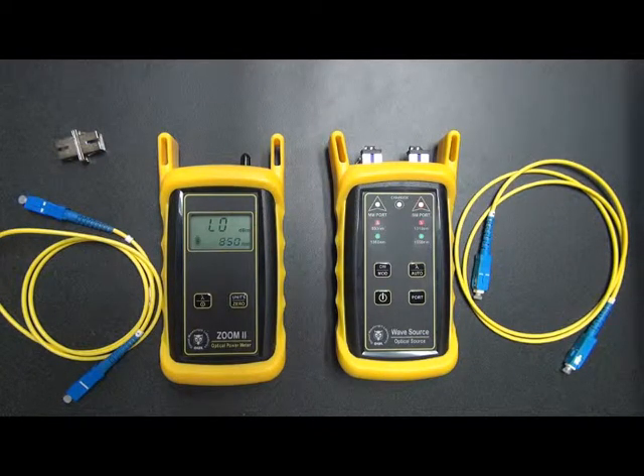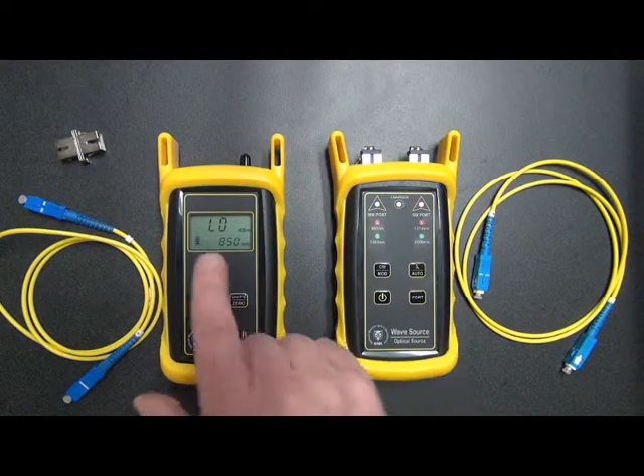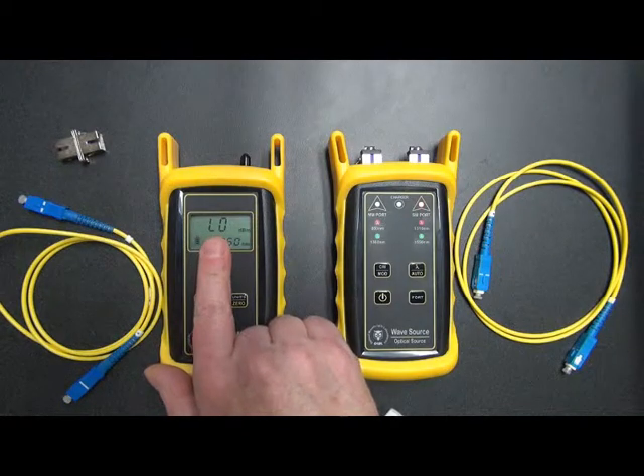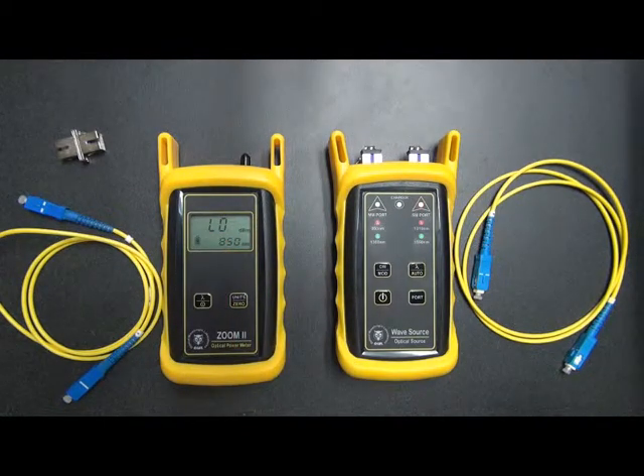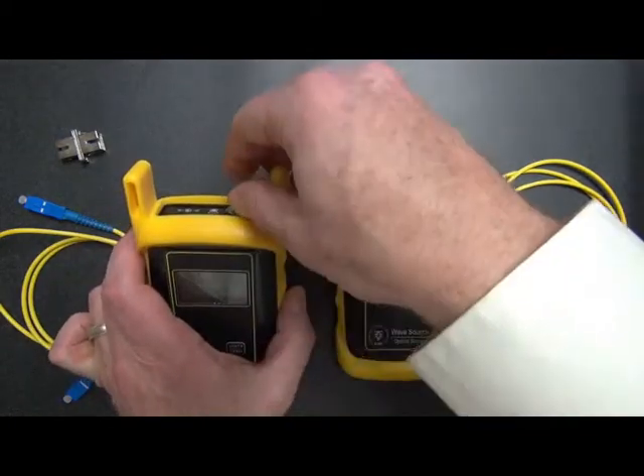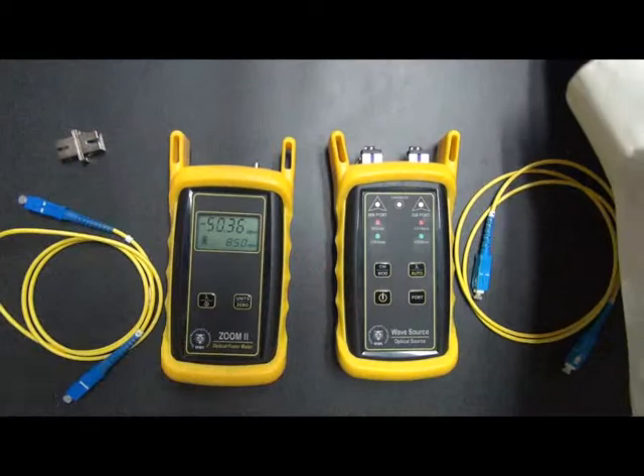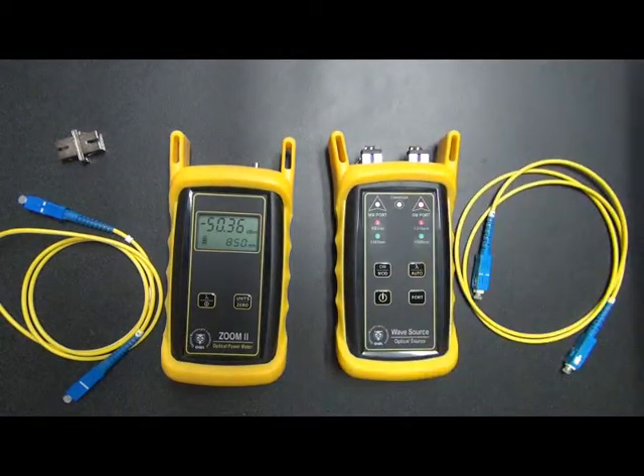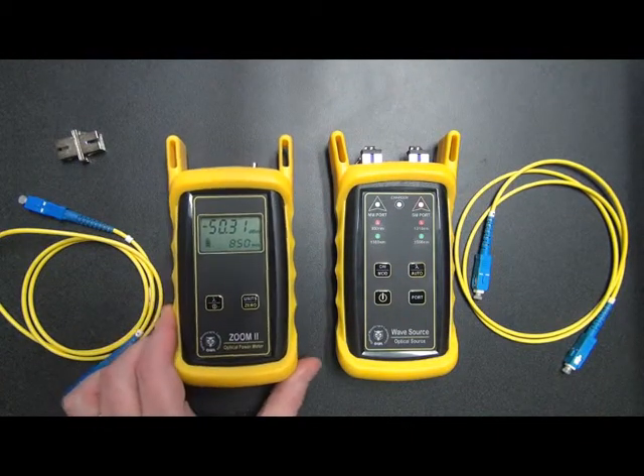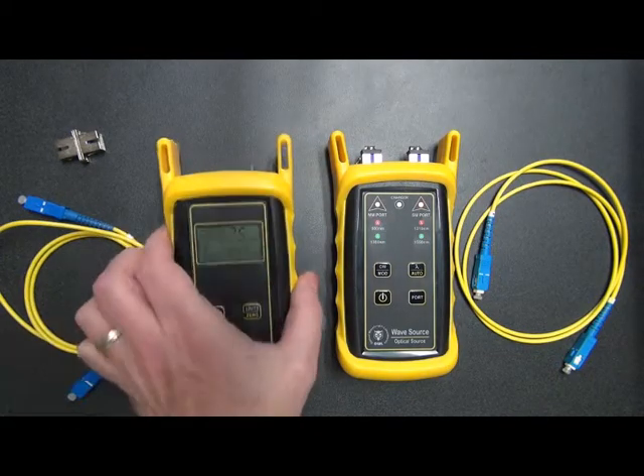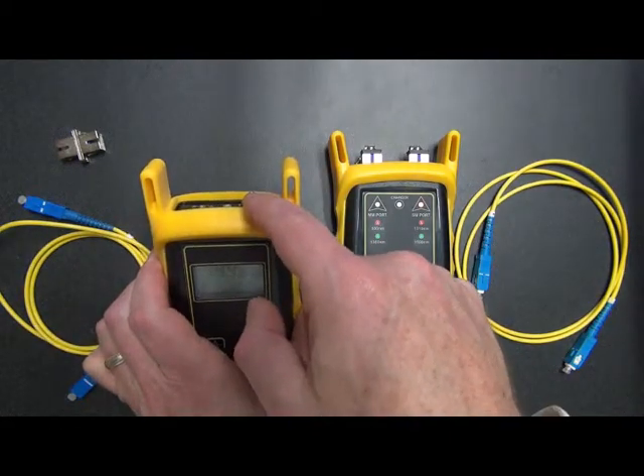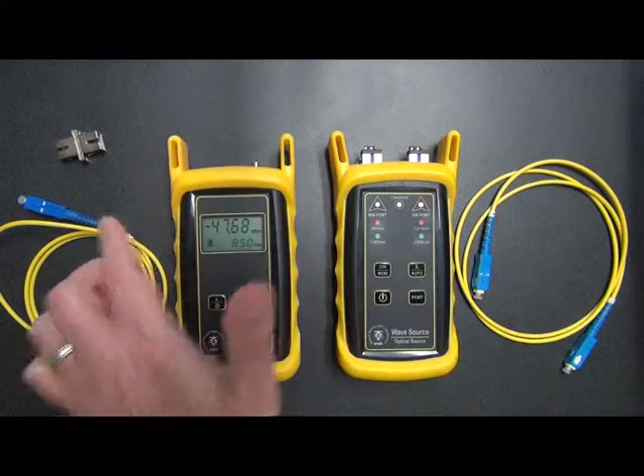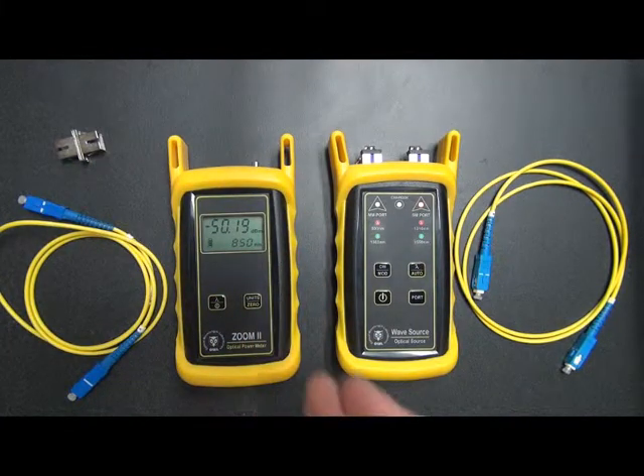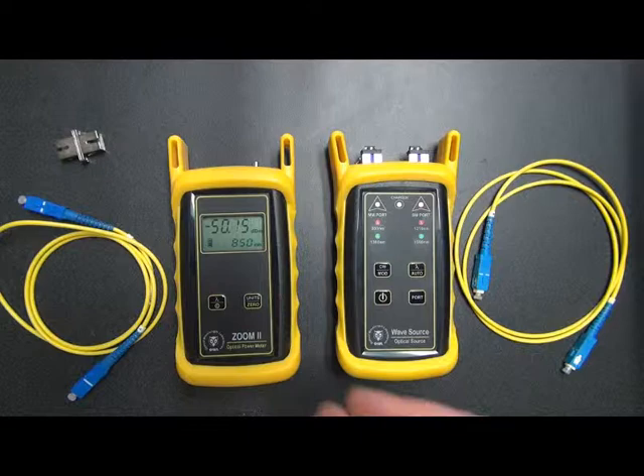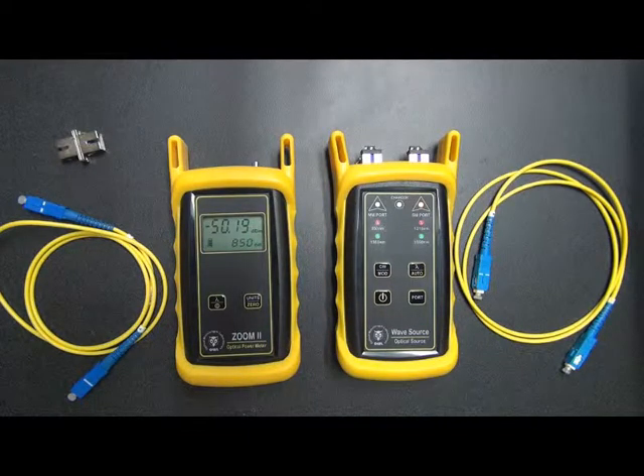Okay, now turning our attention to the Zoom 2, we see that there's a reading of low on the screen. This is normal. What low means is that there's no amount of light coming into the photodetector. It's being blocked by this dust cap here. If we remove the dust cap, we'll notice that we get a reading on the screen. And what we're seeing is the amount of ambient room light entering the photodetector. Obviously there's no connector and no dust cap here, so the only light that's coming in is from the room. So just don't be alarmed, this is normal, and it's a normal power level as well.